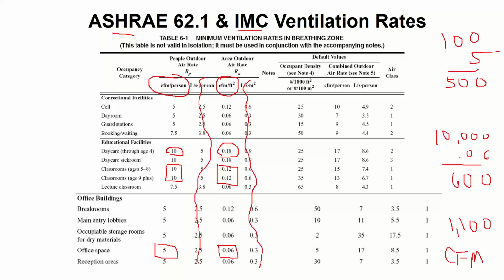somewhat normalness here. Brian typed in a question asking if this is just outside air. Yes, this CFM that we're talking about, so in my example, the 1,100 CFM, that is just the outdoor air requirement, nothing else. The total CFM that your air handling system needs to move, air handling system would mean your rooftop, your air handler, your fan coil, your furnace, the total CFM of air you have to move is dictated by the heating and cooling loads. So we would do a load calculation on the building and the individual spaces served in the building to figure out how much heating and cooling capacity you need, how many BTUs per hour you need to heat this space and cool this space, and then we would select the amount of airflow we need to support those BTUs.